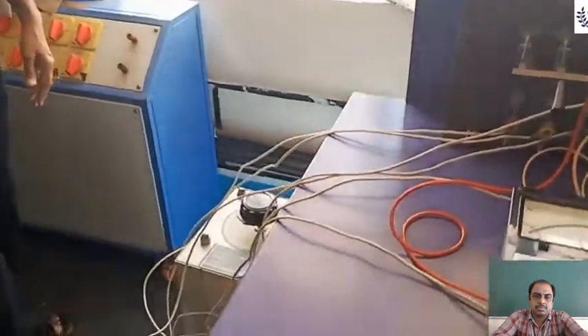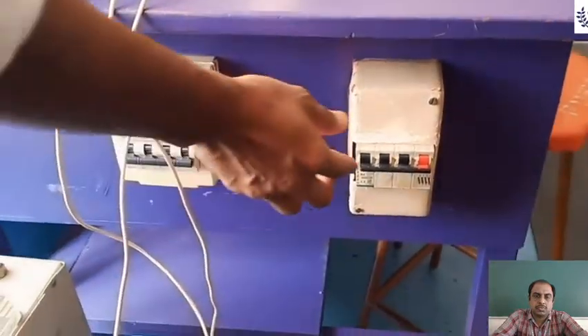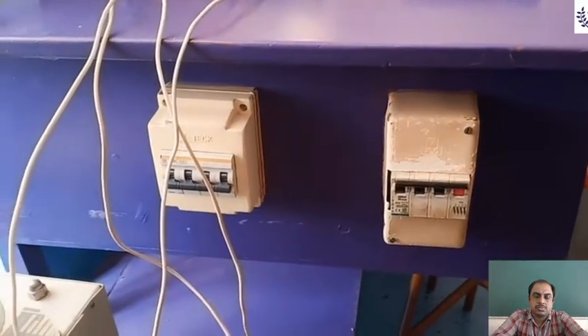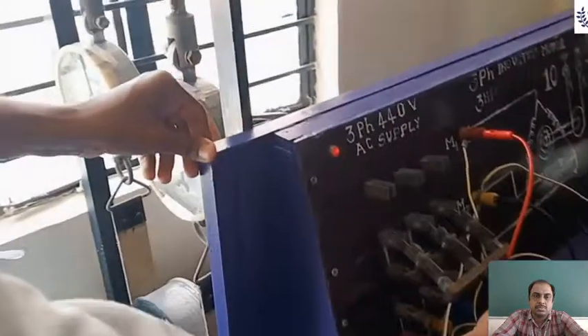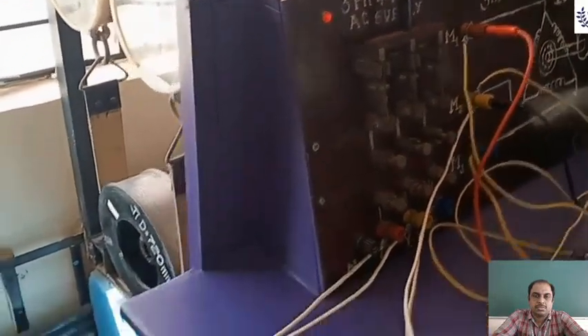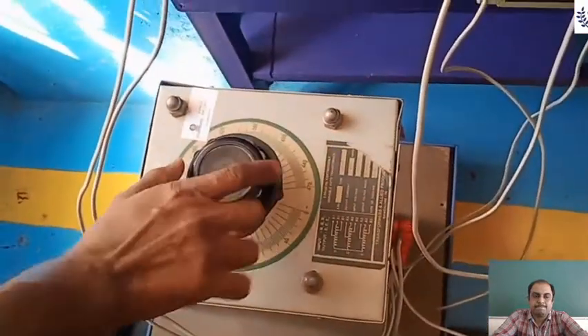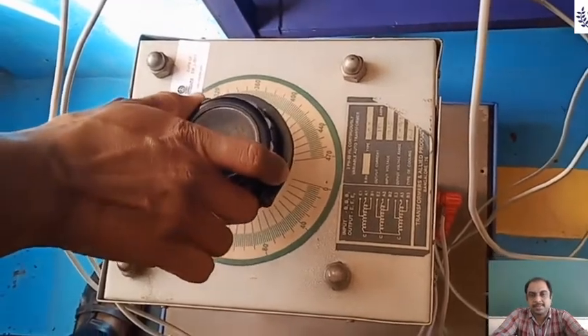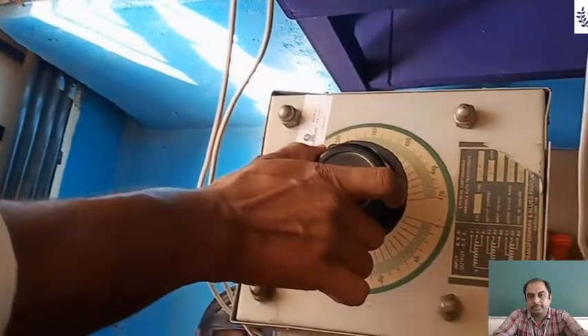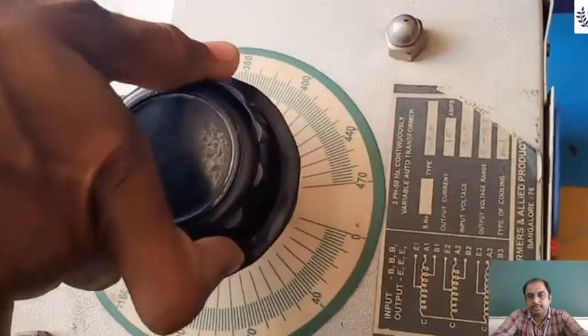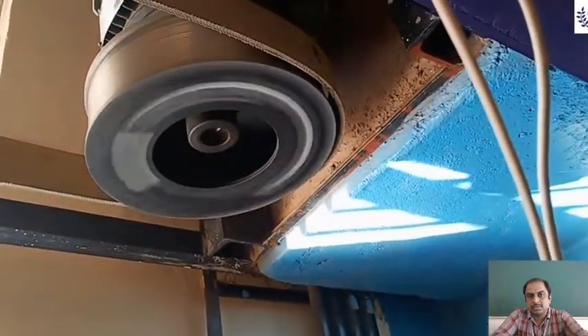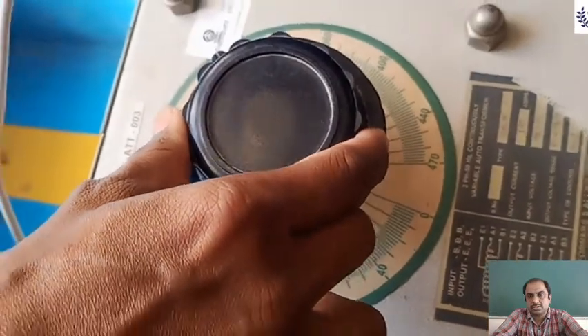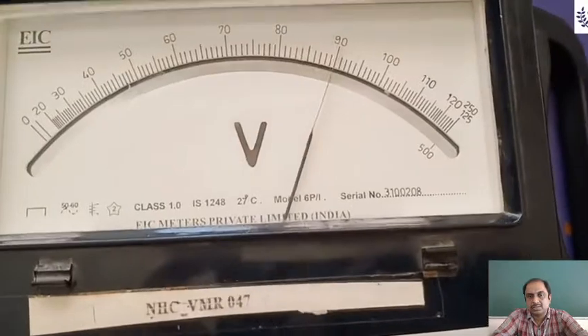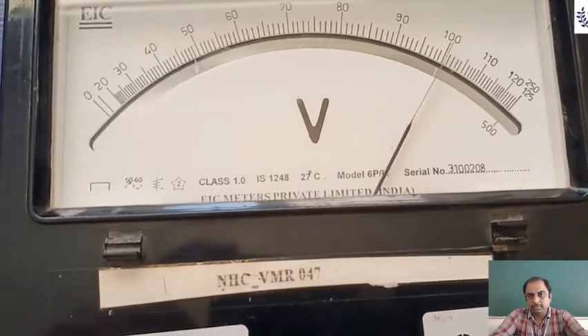First step, we have to switch on the MCB, the miniature circuit breaker. Then we close the TPST switch, triple pole single throw switch. So 400 volt is sent to the auto transformer input. Now we slowly increase the voltage from 0 upward, and as you vary it, you can see the motor speed also varying. The specification of this machine is 400 volt, so we fix it at 400.